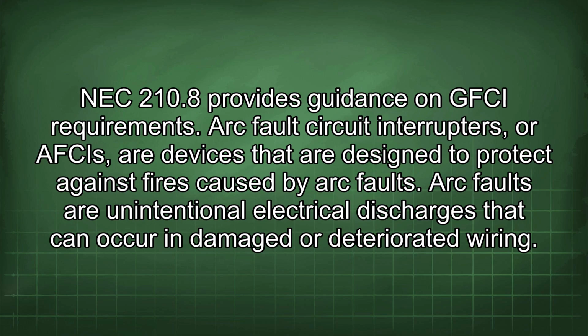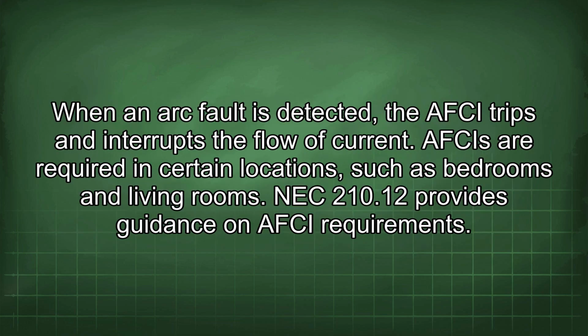Arc fault circuit interrupters, or AFCIs, are devices that are designed to protect against fires caused by arc faults. Arc faults are unintentional electrical discharges that can occur in damaged or deteriorated wiring. When an arc fault is detected, the AFCI trips and interrupts the flow of current. AFCIs are required in certain locations such as bedrooms and living rooms. NEC 210.12 provides guidance on AFCI requirements.